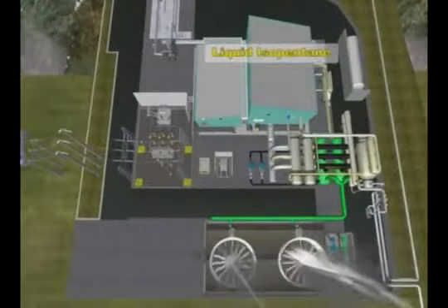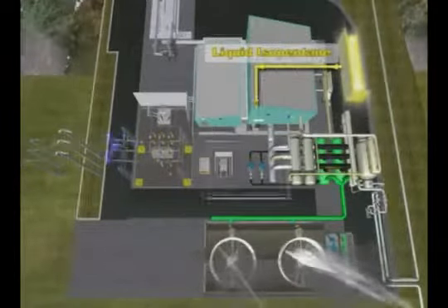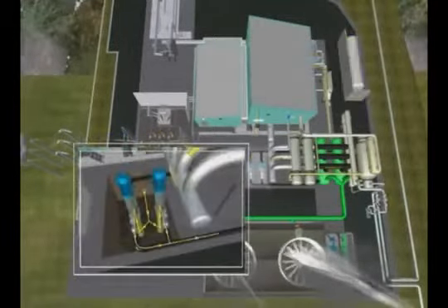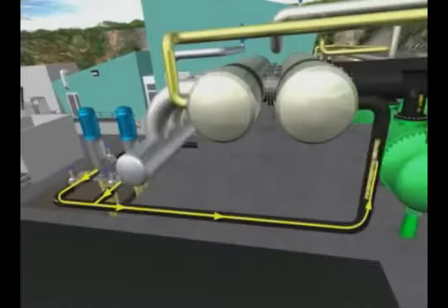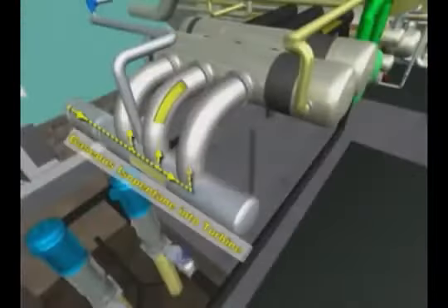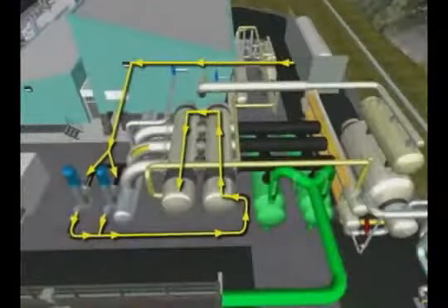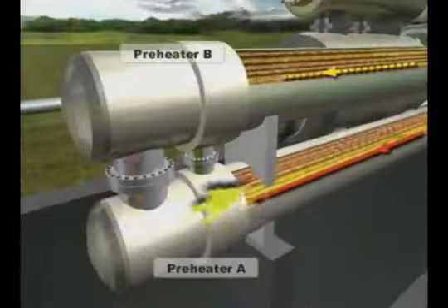On the other side, the isopentane starts its course, leaving the storage tank to a vertical pump, which is sent to the recuperators, where the vaporized isopentane, exiting the turbine, transfers part of its residual heat.